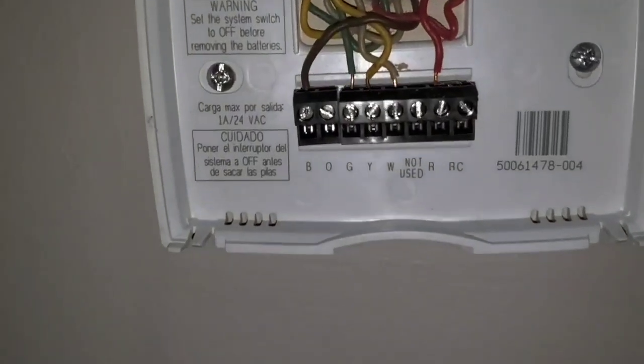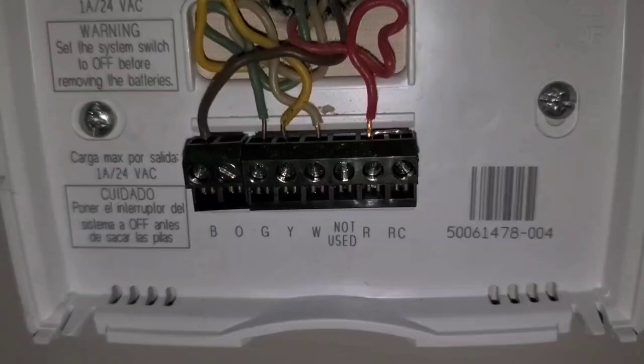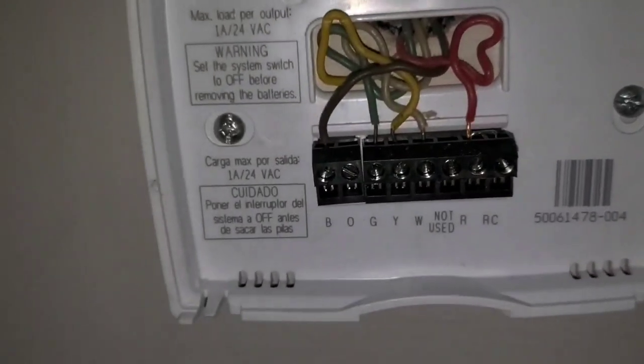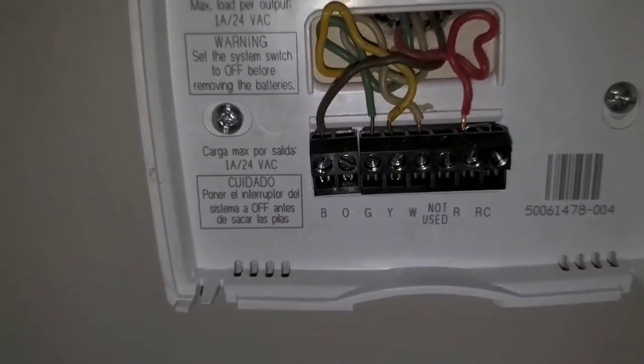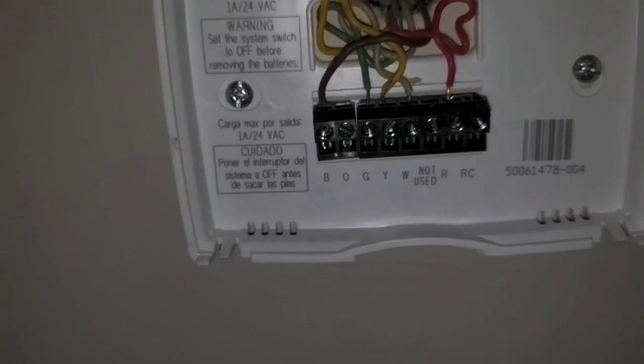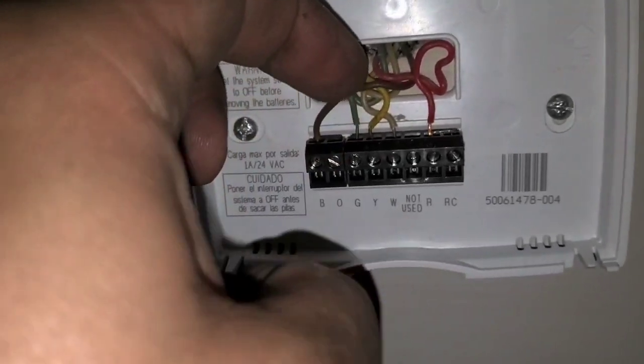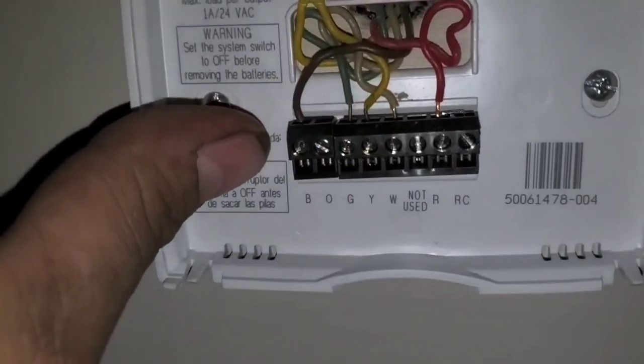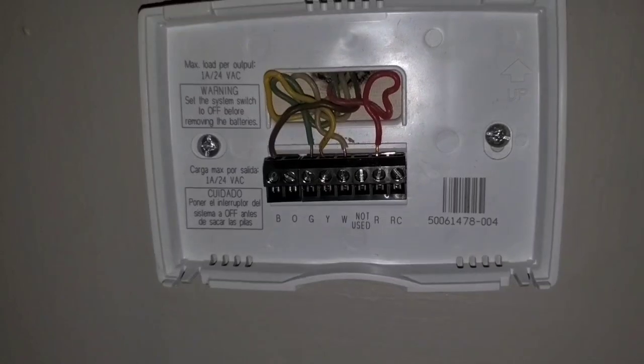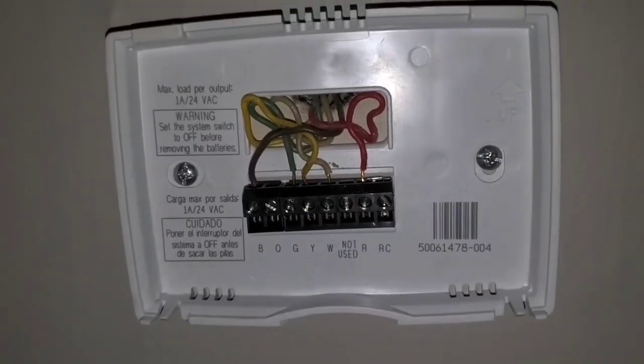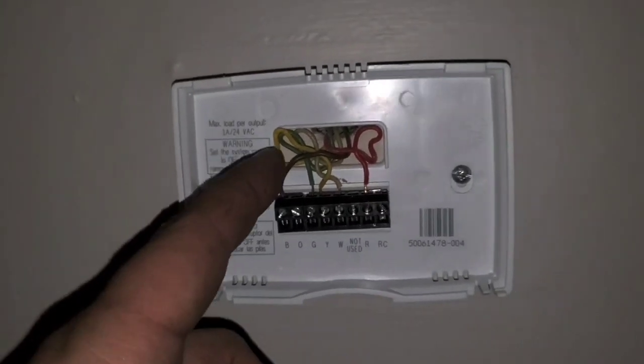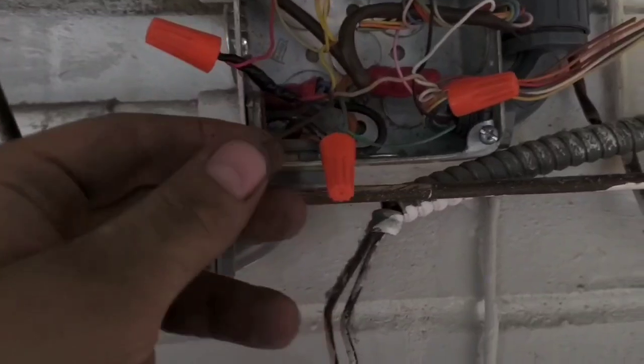Our thermostat connections. This says not used. That's common. Not used. B and O or reversing valves. This system doesn't have a reversing valve. But you see they've got the brown on the B terminal. Basic, everything normal for an air conditioner. Except that's wrong. It's capped off up here.